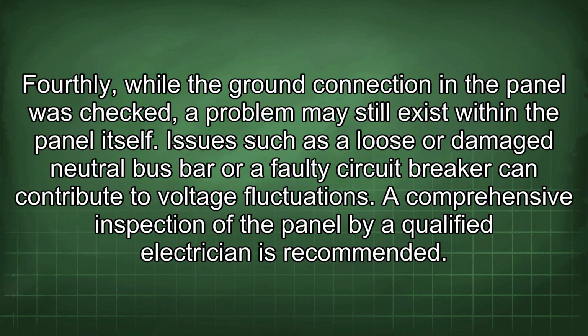Fourthly, while the ground connection in the panel was checked, a problem may still exist within the panel itself. Issues such as a loose or damaged neutral busbar or a faulty circuit breaker can contribute to voltage fluctuations. A comprehensive inspection of the panel by a qualified electrician is recommended.